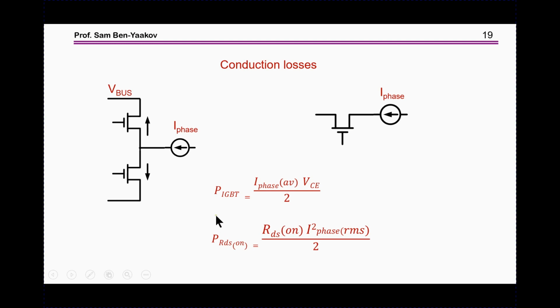In the case of IGBT, the current goes through one element on the average, and the power will be the average, because the IGBT is characterized by a voltage drop during conduction, which I'm calling V sub C. So what contributes to the power is the average phase current times this voltage—this is an approximation since it's still current dependent, but as a first order approximation, this product is the total power in the leg. Then per transistor, since it's AC, half the time it's here and half the time it's there, so it will be divided by 2.